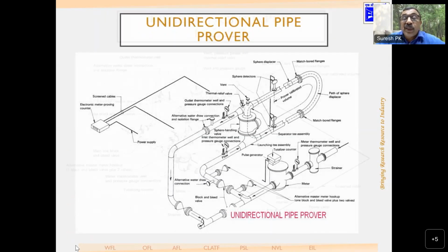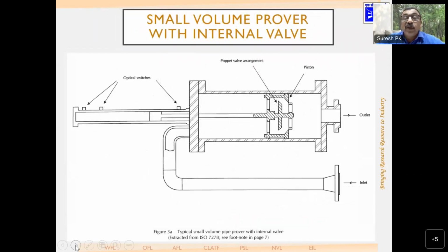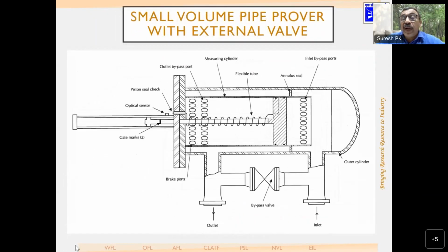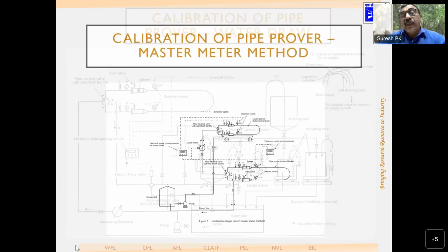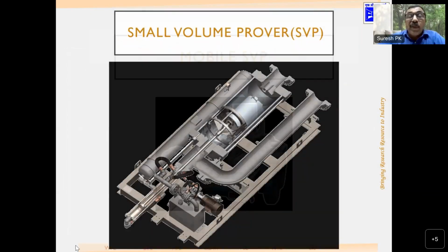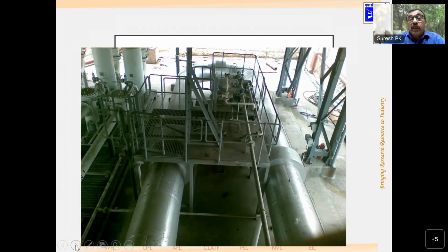So that is a master meter method, which I have. A meter of the highest accuracy is assembled in series with the meter to be calibrated, and the indication from the master meter is used to calibrate the meter to be calibrated.